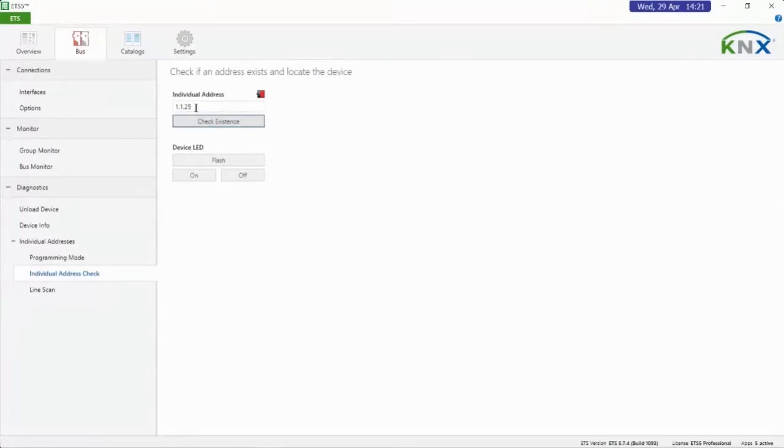Quite simple. That device address is not seen on our bus. Maybe we think it should be there, but it's not there. So why can we not see it? Whereas if I look at 100, which we just checked a minute ago, green straight away. It's polled it. It's answered straight away.